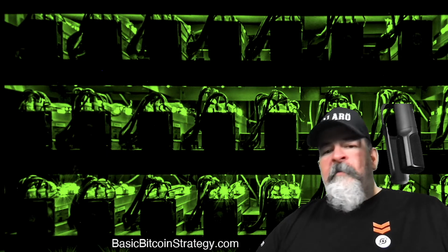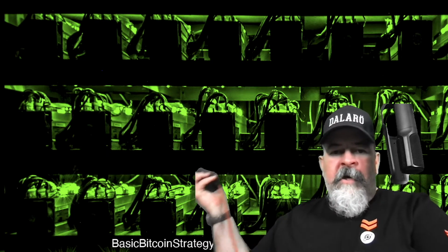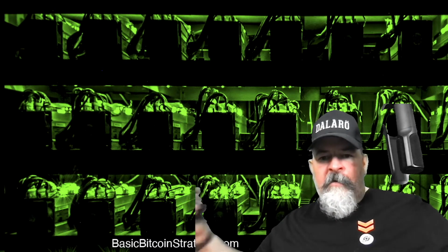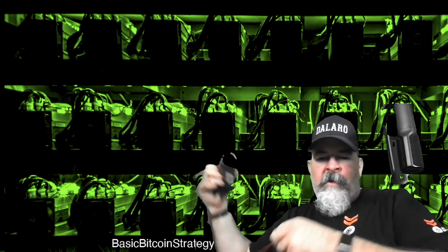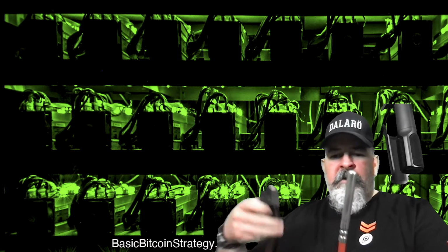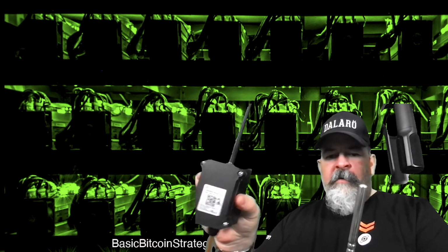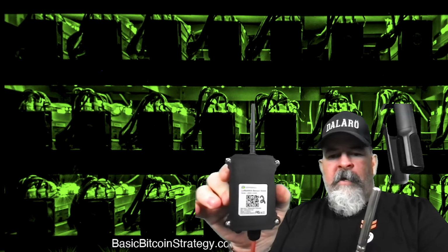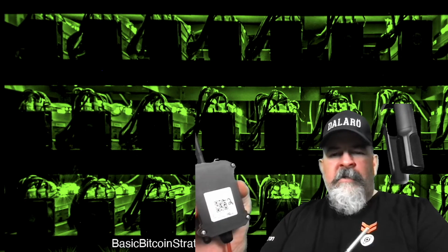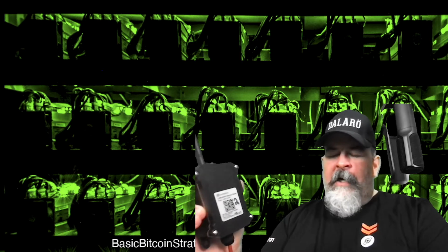So without further ado, I'm going to show you the sensor I picked up for our dry coolers on the roof. Basically this is going to give me water temperature, and it's got quite a long probe here - this probe is a temperature probe, and this is the sensor node. Of course I have a 2 on it because that's going to be dry cooler number 2, right?